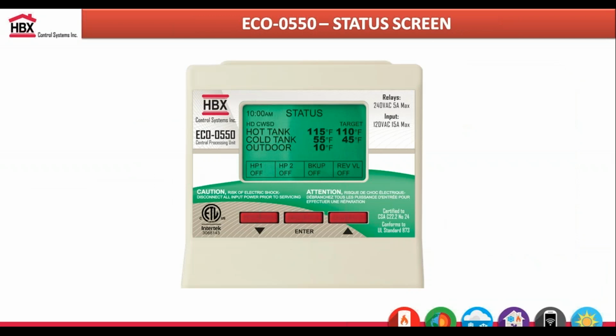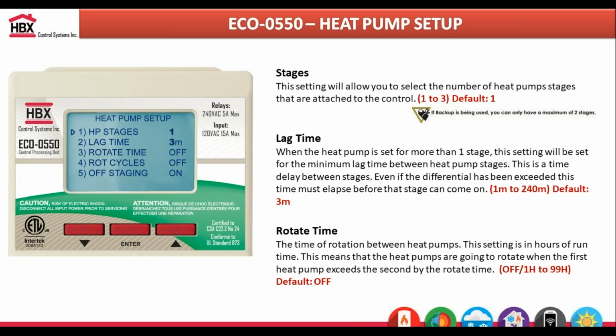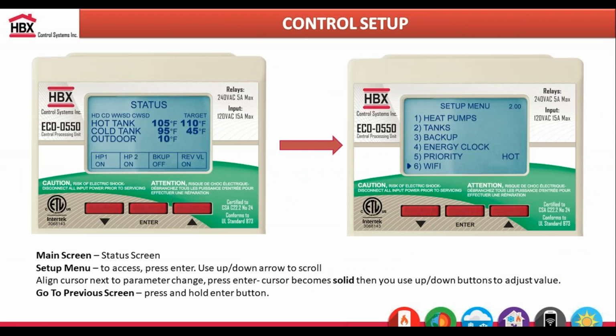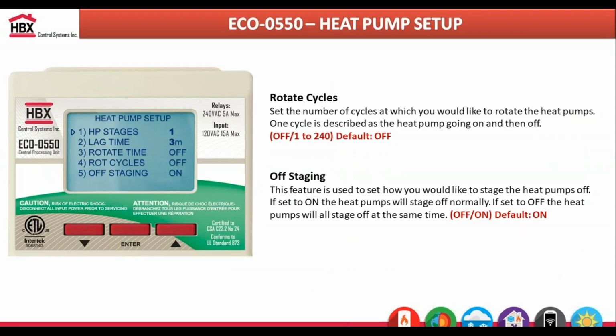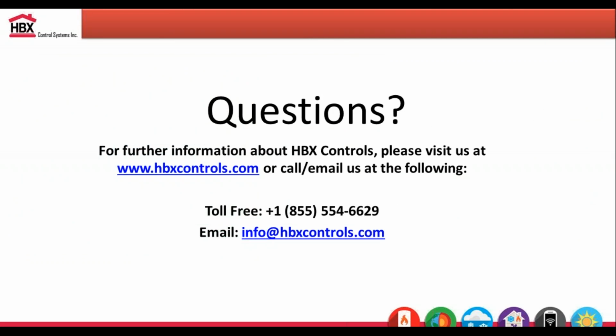We'll go to each control, go through all the settings and how you would wire up through the use of those webinars. So we've already talked about this with our other controllers in terms of the heat pump logic. You can rotate them, you can offstage them, you can have the backup boiler come on based off outdoor temperature or based off tank temperature, or just as a separate lag time. So it really makes it a really easy universal geothermal heat pump controller. So yeah, that's our webinar in a nutshell.